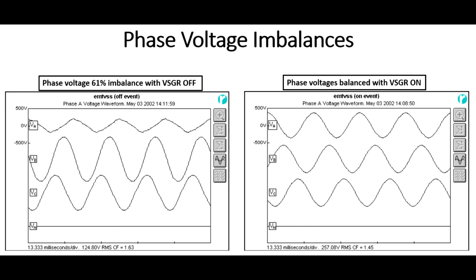In an automotive component manufacturing facility, there was a problem where CNC machines and VFDs would fault continuously. They had a 61% imbalance in the voltages, and the drives saw that as a phase loss, not equal voltages with respect to ground. And you can see on the left side what that graphical waveform looked like. A phase was very low, B was higher than normal, and C was relatively nominal. With the voltage correction on, you'll see all three of those looked very, very clean and relatively the same as each other.